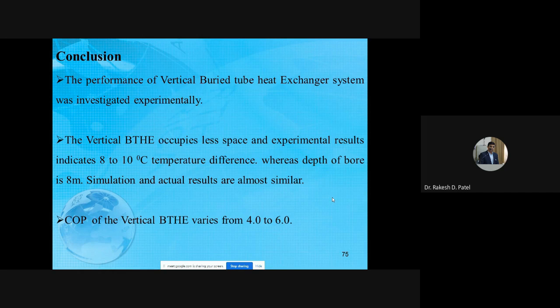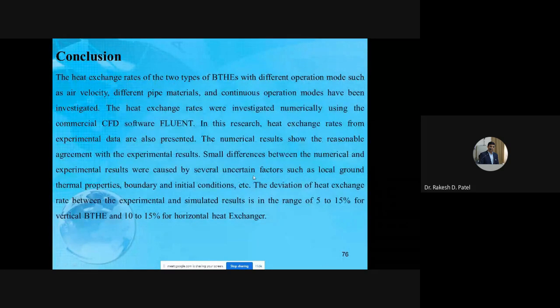So in both conditions, horizontal as well as vertical, the buried depth is the only basic input difference. In the horizontal condition, I'm going only up to 3 to 4 meter, and in the vertical condition, I'm taking the buried depth as 8 to 10 meter. So simulation and actual results are almost similar. The COP of the vertical heat exchanger varies from 4 to 6. The heat exchange rate of the two types of heat exchanger with different operational modes, such as air velocity, different pipe material, and continuous operation mode, has been investigated.